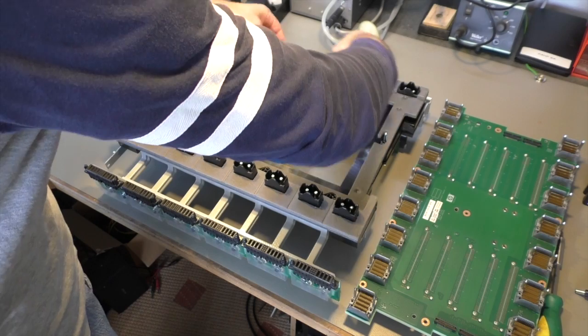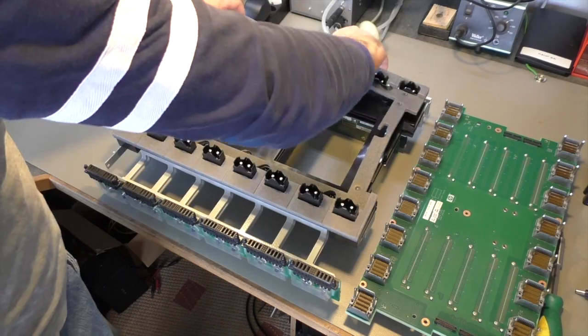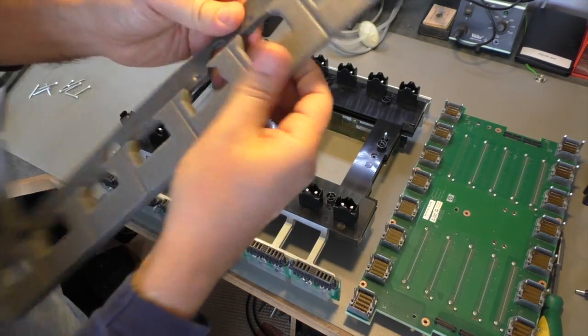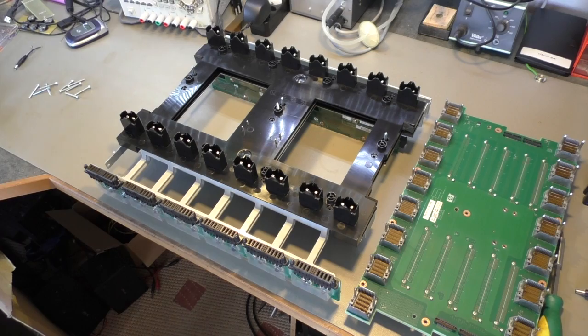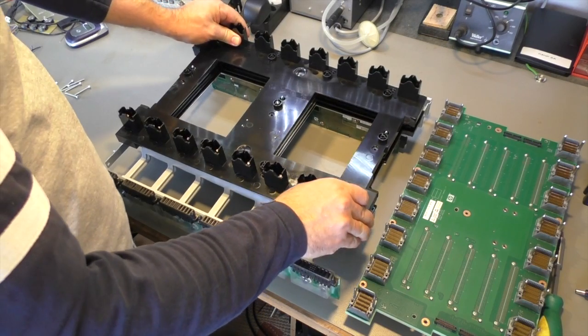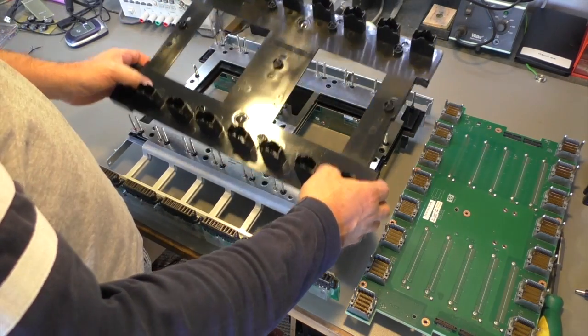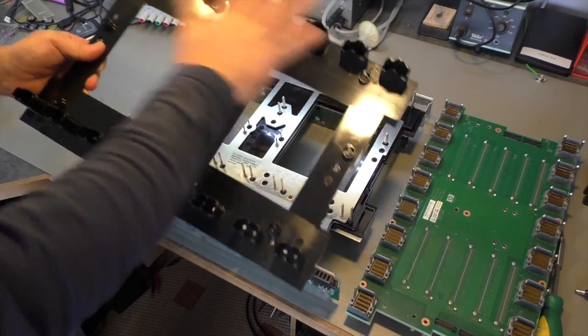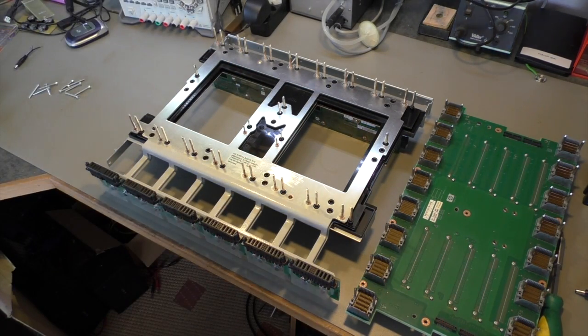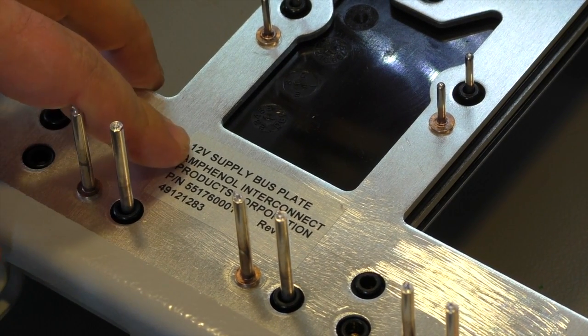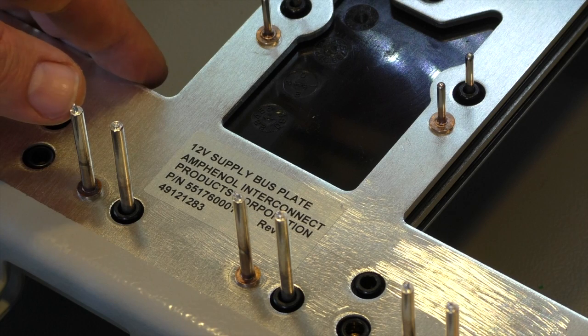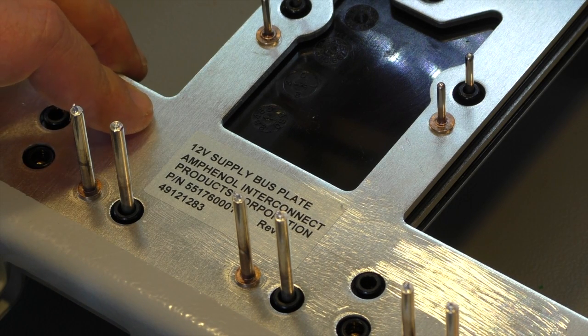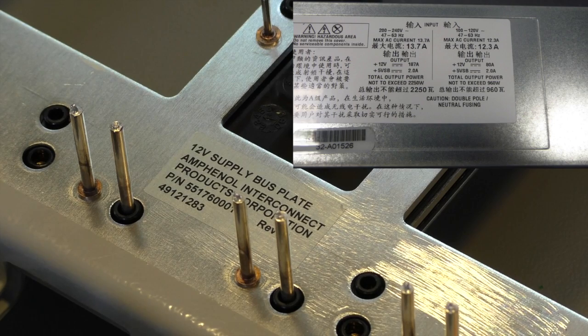Some more sealing - this is just a foam thing. Then we have an insulation plate that protects the power pins and insulates everything from the power backplane. You can read it here - it's a 12 volt power supply. So all the servers, all the IO modules, everything runs on 12 volts. The power supplies are delivering 12 volt and also 5 volt, but only as a standby supply.